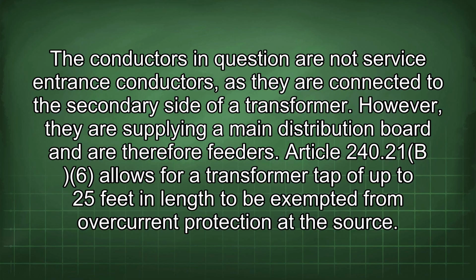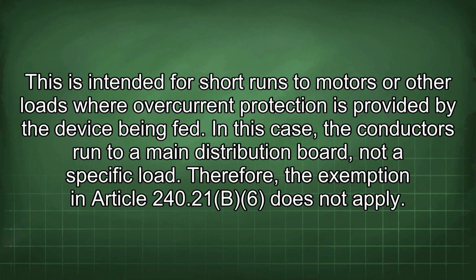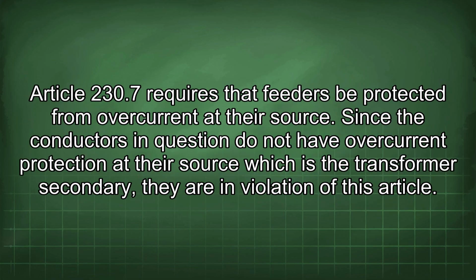240.21(B)(6) allows for a transformer tap of up to 25 feet in length to be exempted from overcurrent protection at the source. This is intended for short runs to motors or other loads where overcurrent protection is provided by the device being fed. In this case, the conductors run to a main distribution board, not a specific load. Therefore, the exemption in Article 240.21(B)(6) does not apply. Article 230.7 requires that feeders be protected from overcurrent at their source.